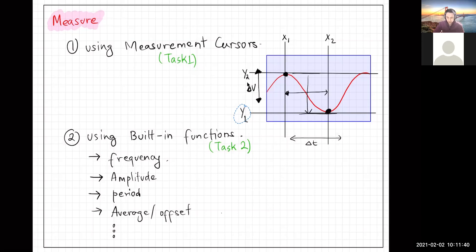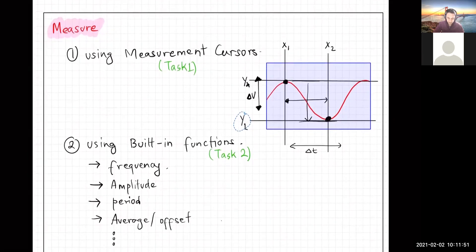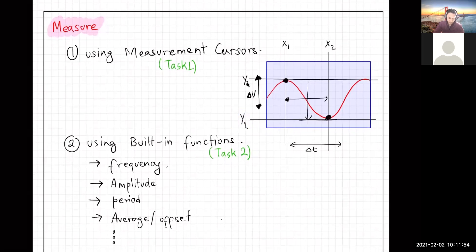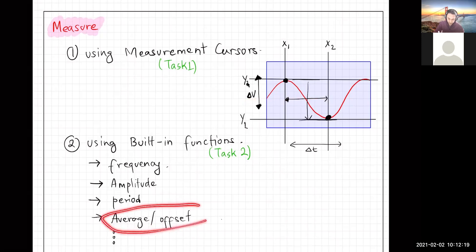The built-in functions use algorithms to calculate measurements without cursors. Examples include frequency, amplitude, period, and average. Average is something difficult to measure with just cursors, since you can never quite center them exactly. The built-in function takes all the data, performs the integration, and calculates the true average of the signal.